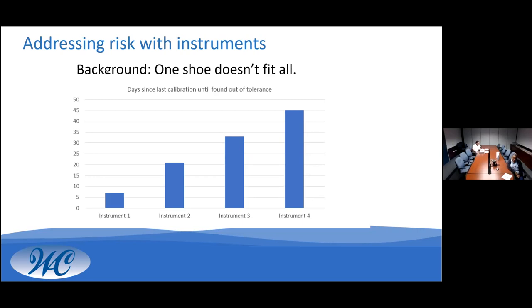The instruments were assigned for a full check and calibration on a fixed once-a-month schedule that was rotated between our lab technicians. As mentioned in section 6.4.10, we perform intermediate checks and continuing calibration verifications. Between calibrations, it was found that some instruments had drifted out of their accepted tolerance, while some missed their due date for a monthly calibration and still passed verifications on a weekly basis. The manufacturer's recommended interval of 30 days was appropriate for some instruments, as you can see, but not all of them. We suspect the cause to be that some locations have matrices and operators that deteriorate sensors much faster than expected, while some have near perfect operating conditions.